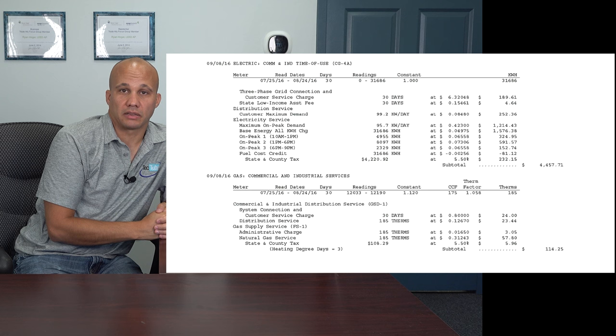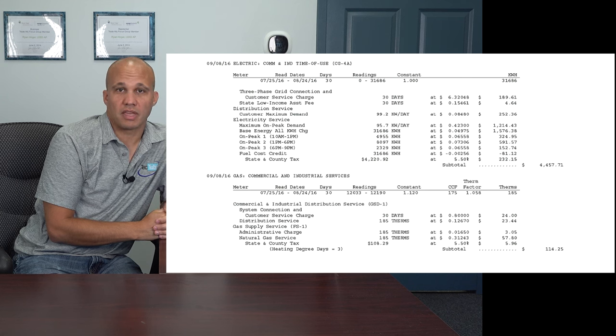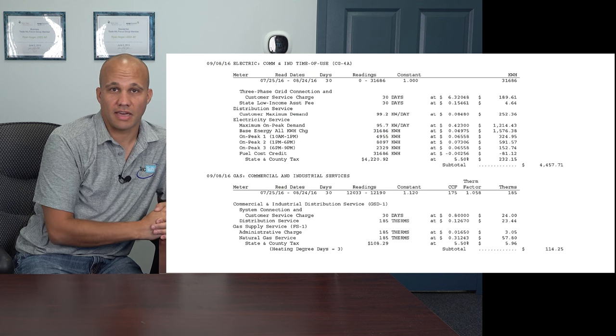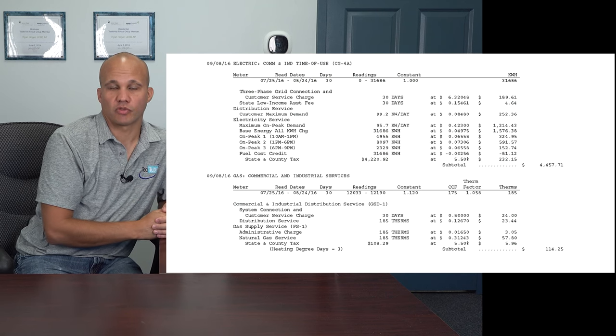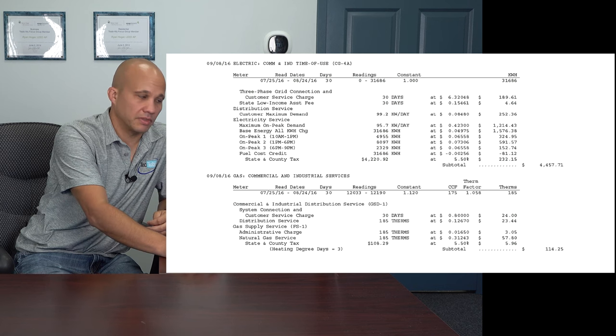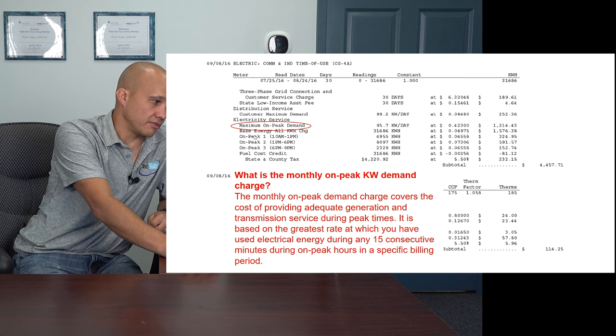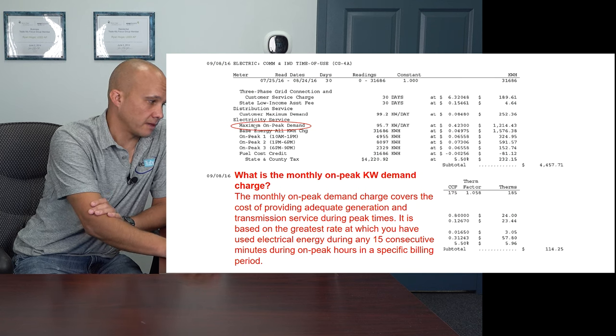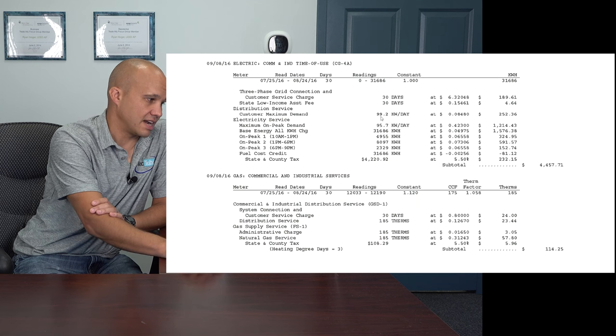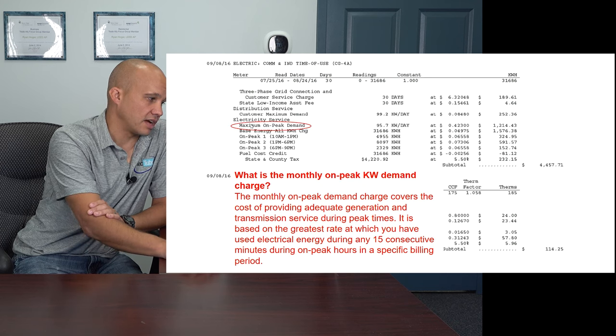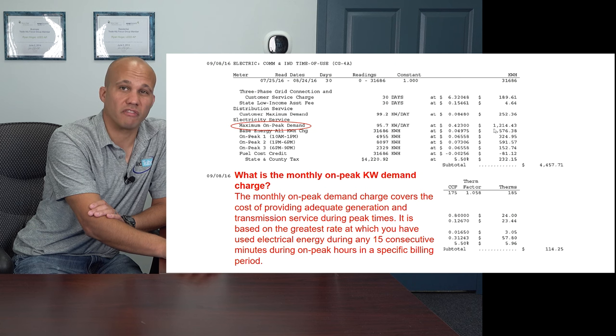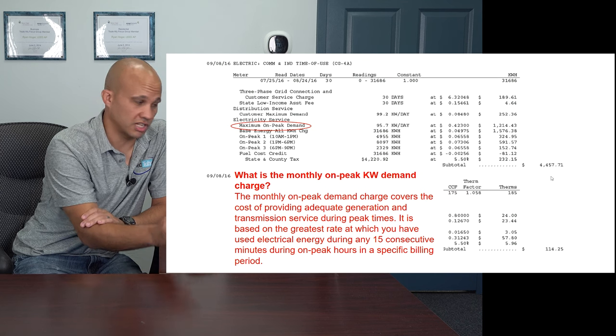They want you to keep KW demand low, because if you're a big user and always spiking, you force them to make infrastructure upgrades to the physical wiring of the community, which is expensive. Looking at this bill: the distribution demand charge is 99.2 KW at 8.4 cents — that's $252 that month. And then the electricity demand charge is 95.7 KW — another $1,200. So on this person's $4,500 bill, about $1,500 of it is going towards demand charges and the rest towards actual energy usage.